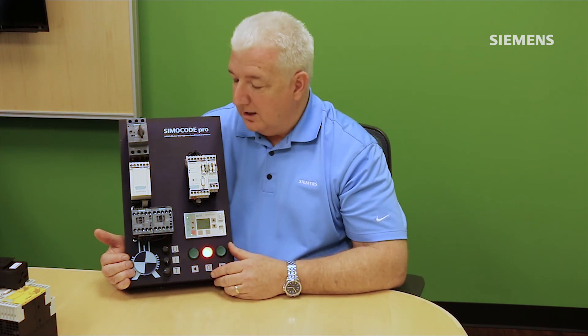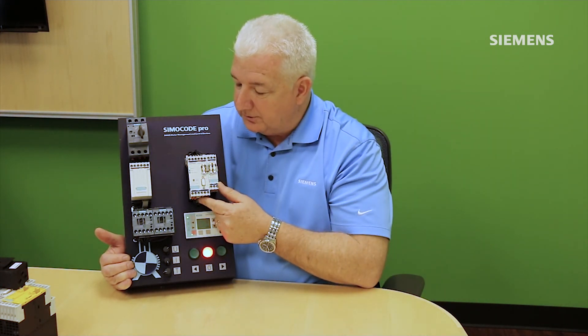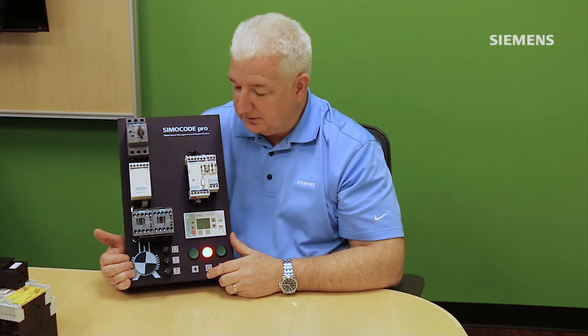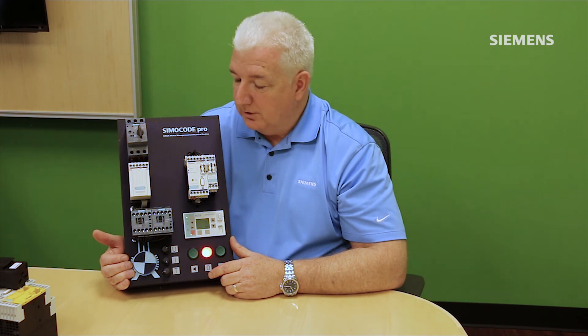SIMOCODE pro is also easy for maintenance personnel, thanks to a two-piece design with a separate memory module containing the complete configuration including the network address. For replacement, you remove the removable terminals without touching any three-phase wiring, bring in the new device, plug in the memory module, and the system is back up in minutes — rather than the 30 to 45 minutes typical of a conventional replacement.